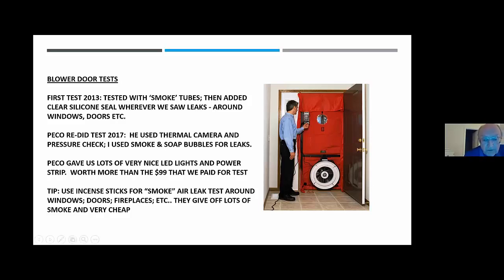I do have a tip. If you run the blower door test, it's not enough just to run the pressure drop. You really need to walk around with some type of smoke tubes. I've found if you get incense sticks and light 2 or 3, you get a nice smoke, and you can watch as it moves, if the air currents move around windows and doors and fireplaces. They're very cheap to use, and I thought very safe.